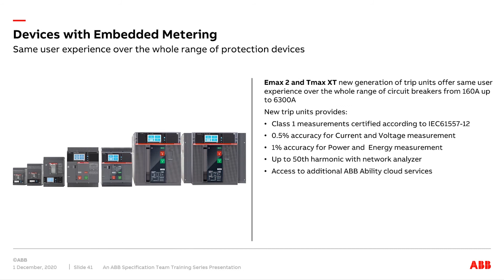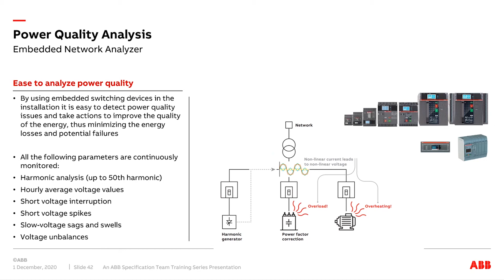Picking up on the analysis, as well as actual energy consumption, we can look at many other parameters associated with the electrical network, such as harmonic analysis. We can look at average values and plot those, and look at disturbances in the electrical network such as voltage interruptions, spikes, sags, swells, and voltage imbalances—all issues which affect the efficiency of the electrical network and its associated devices.